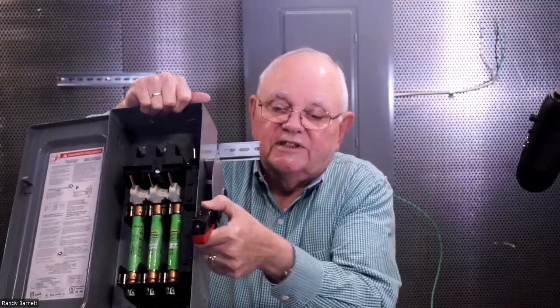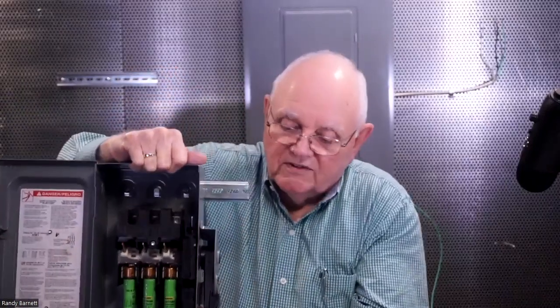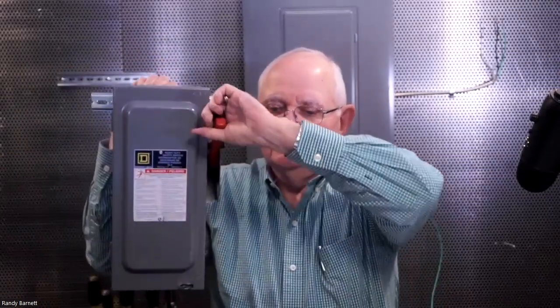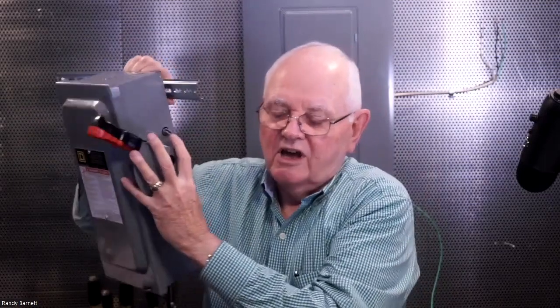Well, that's true. If I try to operate the handle right now, there's an interlock down here that prevents that from happening. And the same way, I can go ahead and close the switch, and then close the door, and then I can operate the switch, but I can't open the door now with that switch in the on position. I've got an interlock over here on the side that I would have to turn and override in order to get that to work. So it meets the definition of a safety switch.